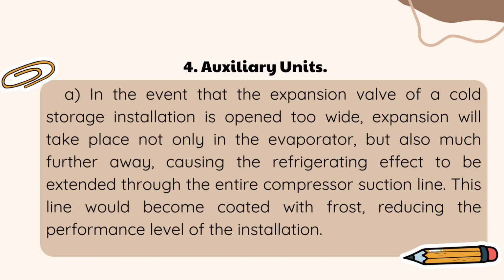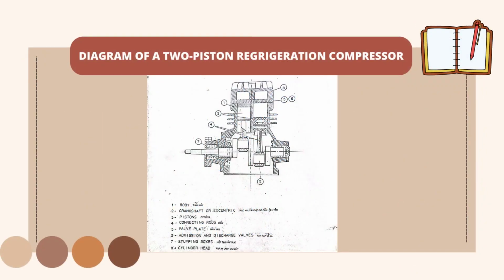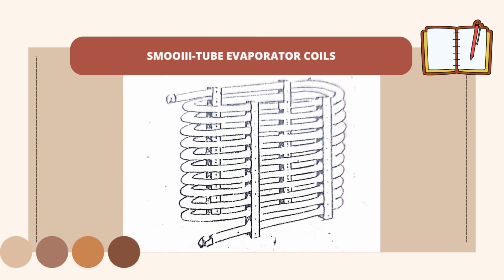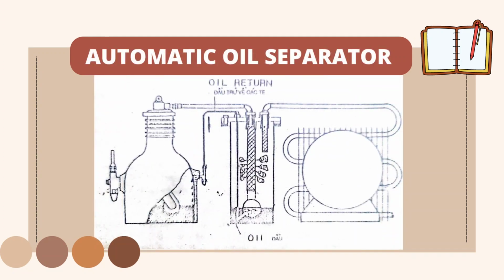4. Auxiliary units. A. In the event that the expansion valve of a cold storage installation is opened too wide, expansion will take place not only in the evaporator, but also much further away, causing the refrigerating effect to be extended through the entire compressor suction line. This line would become coated with frost, reducing the performance level of the installation. Diagram of a two-piston refrigeration compressor. Smooth tube evaporator coils. Automatic oil separator.